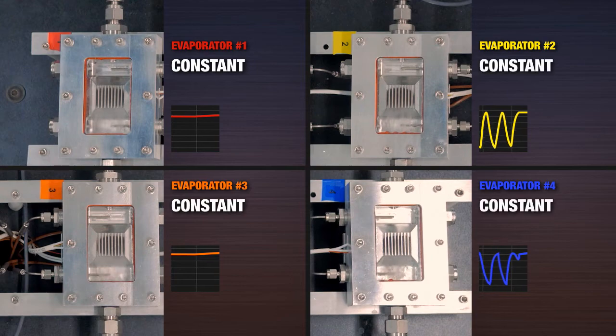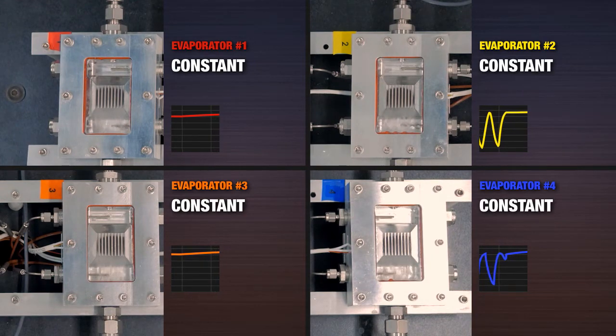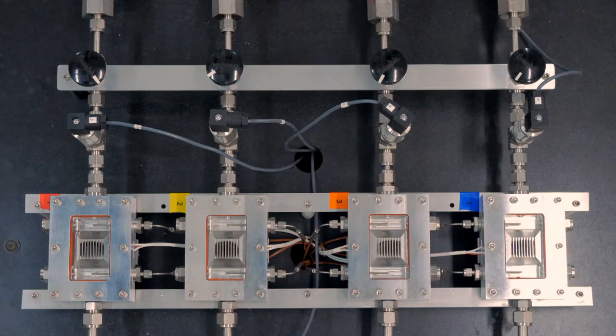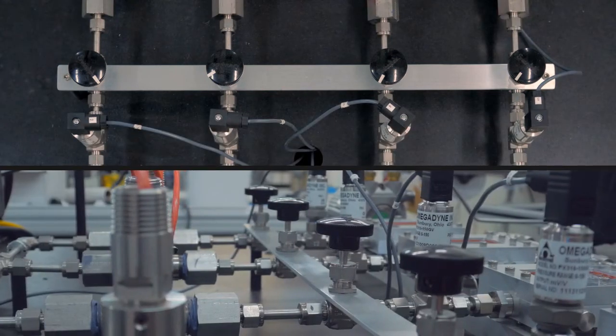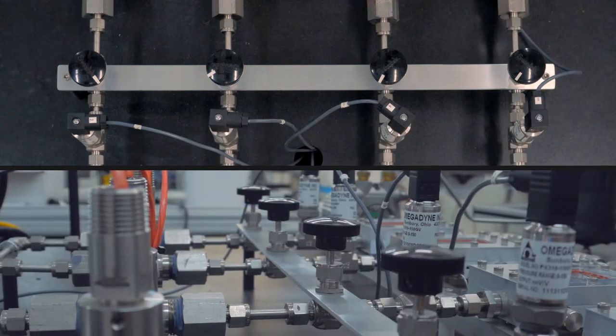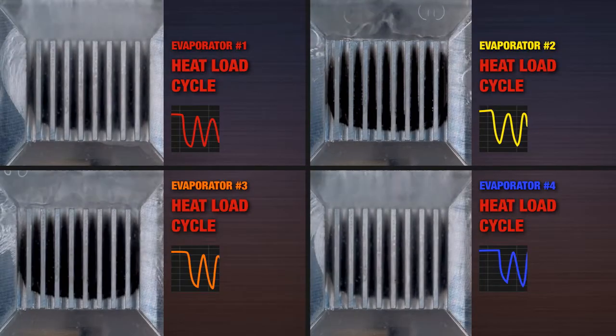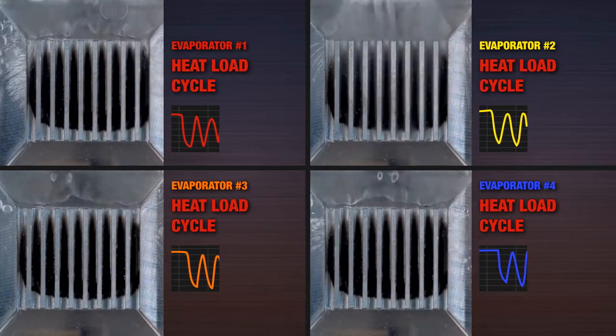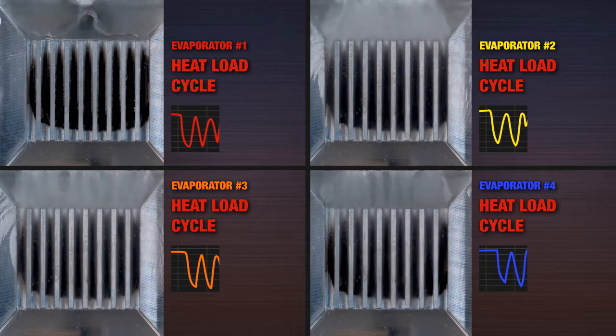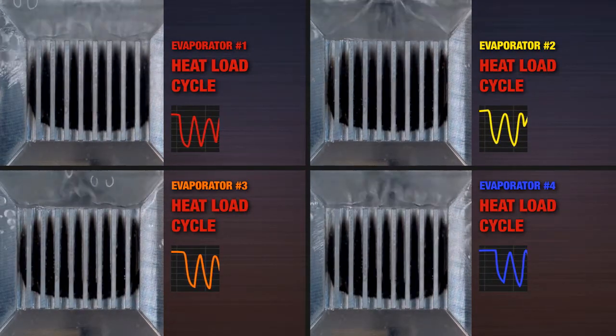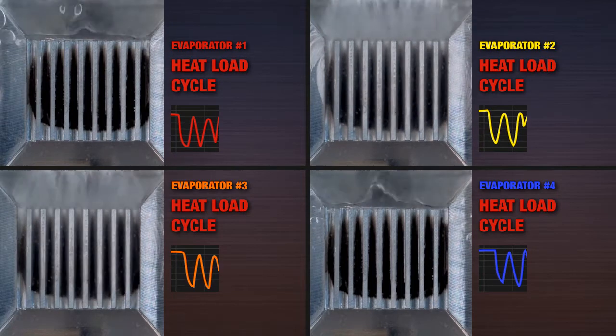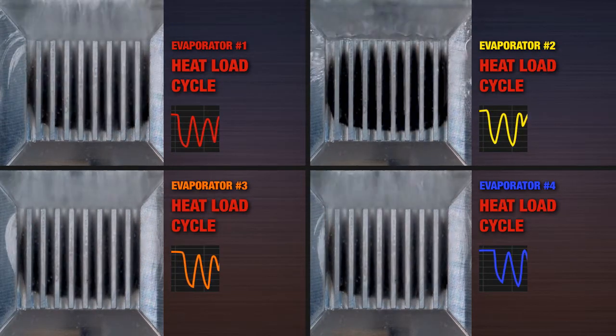Now we stop cycling the heat loads and see that all four evaporators are stable with constant heat load. A key feature that enables this flexibility was achieved by placing flow restrictors in front of the evaporators. We can ensure that each of the evaporators receives the appropriate amount of coolant. This allows the performance of the other evaporators to remain unchanged as heat is applied to different evaporators at different times, ensuring that each evaporator provides adequate cooling to the device as the other devices turn on and off.